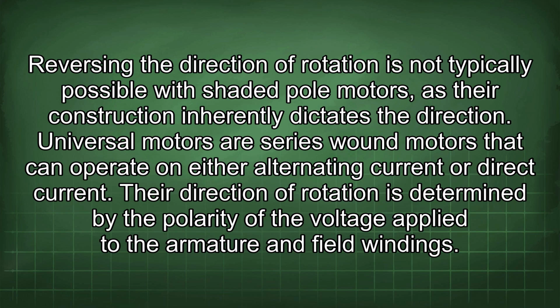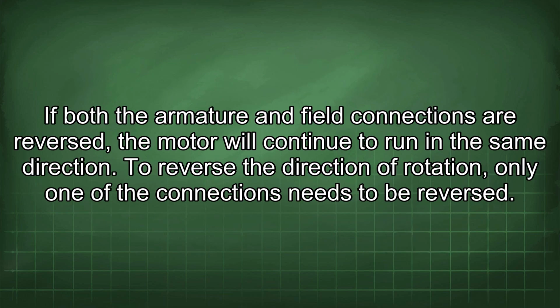Universal motors are series-wound motors that can operate on either alternating current or direct current. The direction of rotation is determined by the polarity of the voltage applied to the armature and field windings. If both the armature and field connections are reversed, the motor will continue to run in the same direction. To reverse the direction of rotation, only one of the connections needs to be reversed.